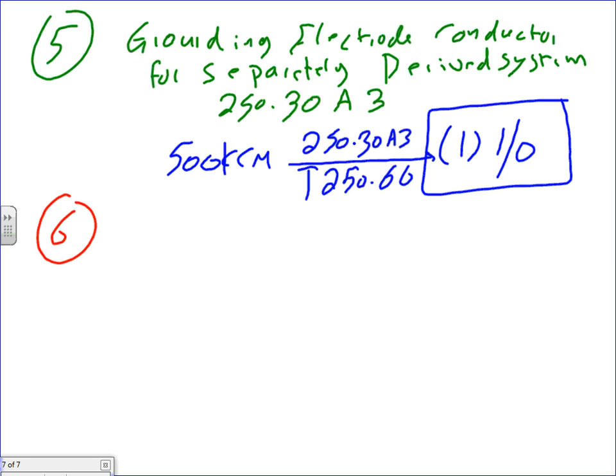The second one, guys, the main bonding jumper, they call it grounding separately derived system alternating system bonding jumper. I have mine as 250.30(A)(1), is it the same? For your main bond, in this case it's called the system bonding jumper, not main. The main bonding jumper is for the service.